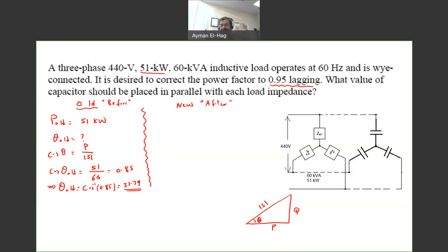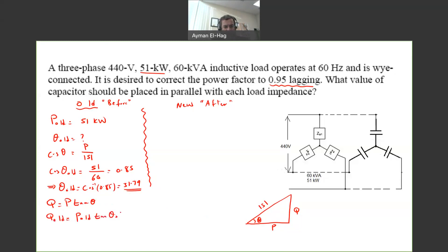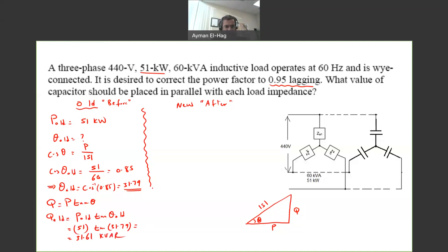Now we find Q_old. Using the relation Q = P·tan(θ), we get Q_old = P_old × tan(theta_old) = 51 kW × tan(31.79°), which gives 31.61 kVAR. So we are done with the old values: P_old, theta_old, and Q_old.